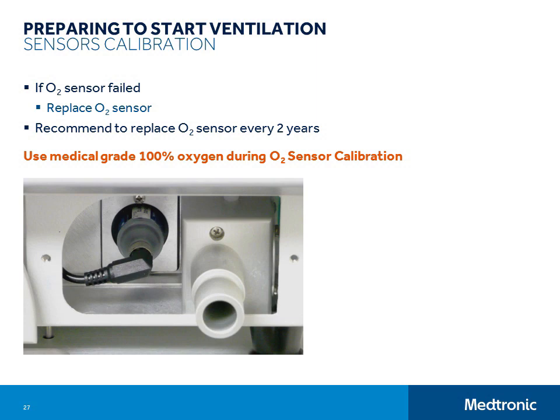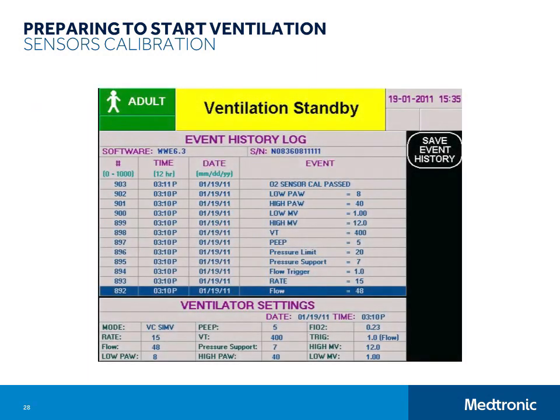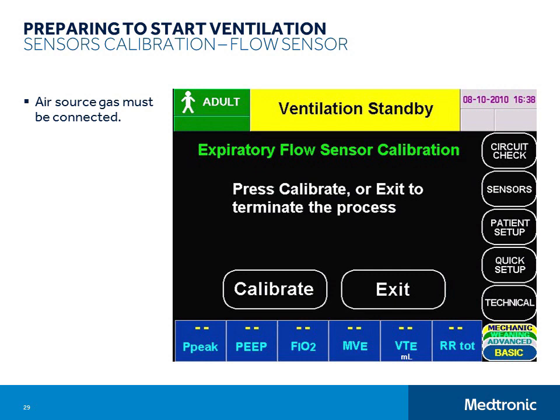Even though you won't be doing the flow sensor cal at startup, let's go through the process so you know how to do it. Enter the sensor screen just as you did when accessing the O2 sensor cal. Touch the flow sensor button, then touch Calibrate to start the calibration process. The message display will indicate if the sensor passed or failed the calibration. If it passes, touch Exit.